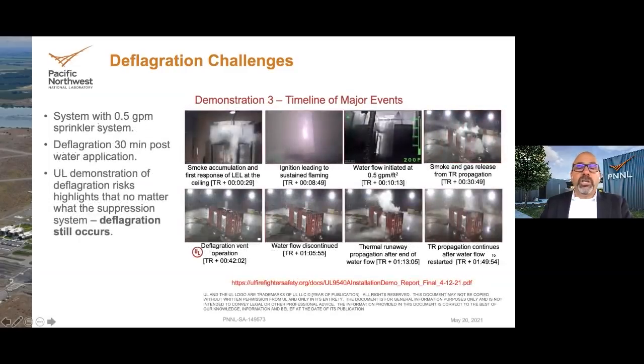In the next demonstration, they're actually using a water suppression system, triggered by smoke and heat. It's triggered by heat because there's a fire sprinkler in there, so it's got a bulb that has to activate. There's a little bit of a delay from the onset of thermal runaway to the sprinkler head discharging, about 8 minutes. Water flow at 0.5 gallons per minute per square foot — it's a significant amount of water flow.